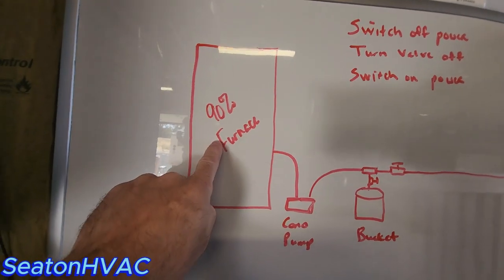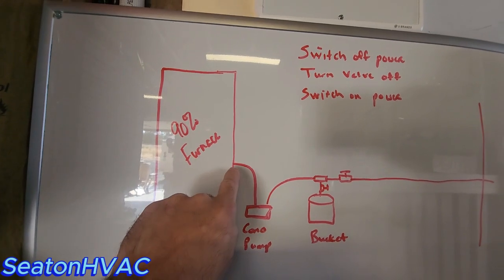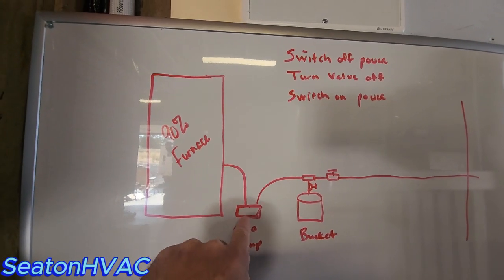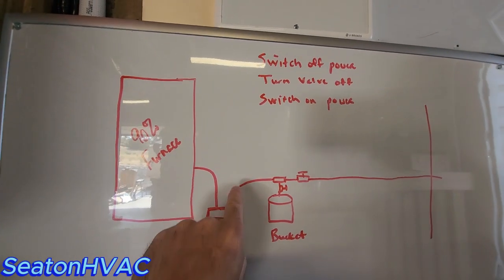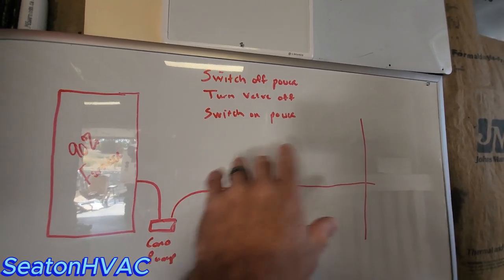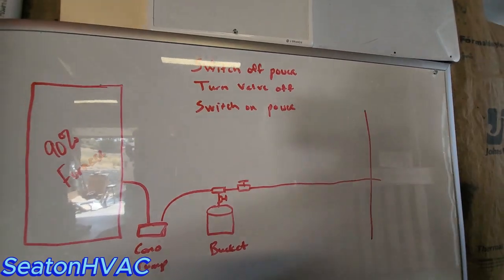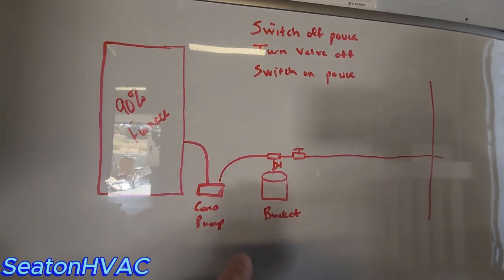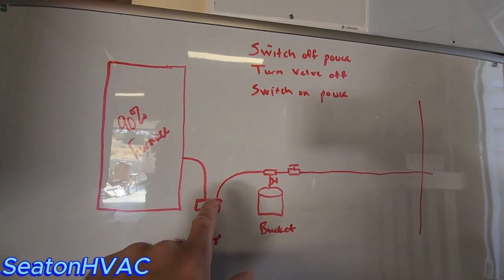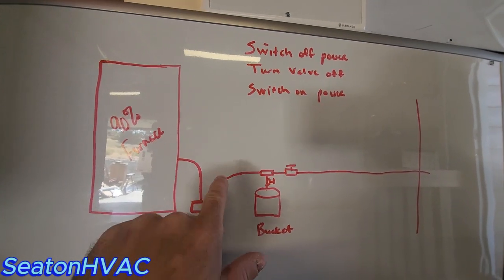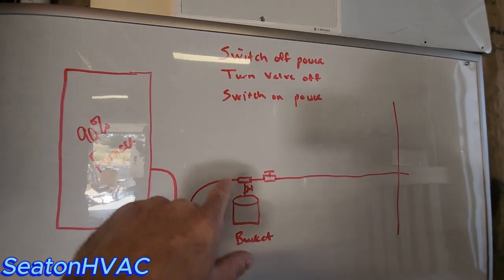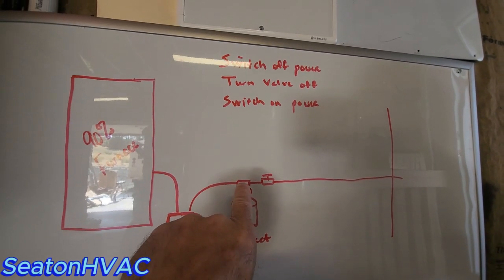So you've got a 90% furnace here. Let's say the PVC drain goes into a condensate pump, and then your vinyl tubing goes outside, or maybe it even converts to PVC. That'll still freeze under extreme conditions. So let's do a condensate pump scenario - say you've got your vinyl tubing going out. What you can do is convert your tubing.